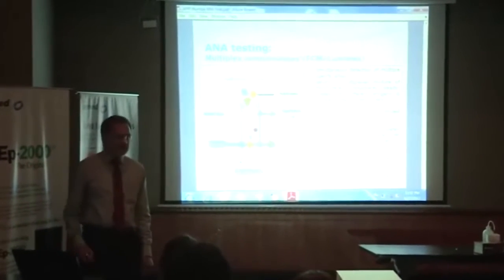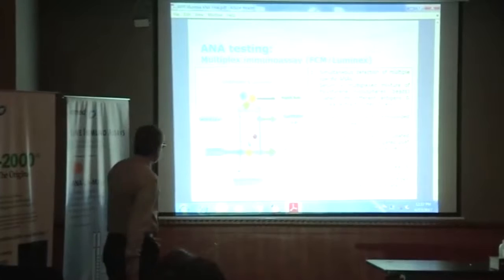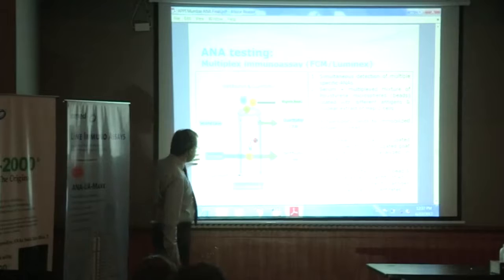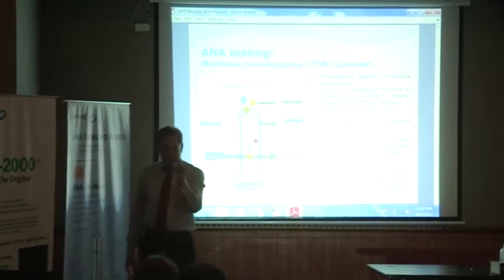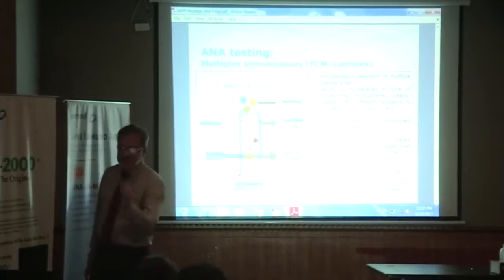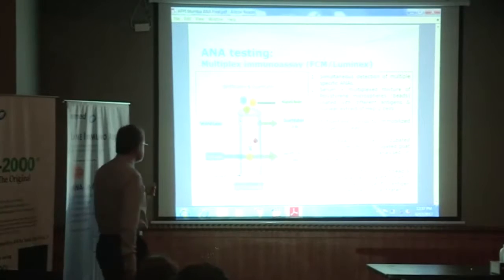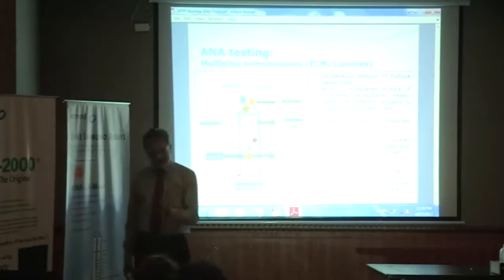The beads are coated with them, and when the antigen-antibody reaction takes place and you run it through the flow cell, first a laser comes which identifies the bead. From identification of the bead with the first laser, the antibody is identified, and the second laser quantitates the antibody. So first is which antibody, second is quantitation.